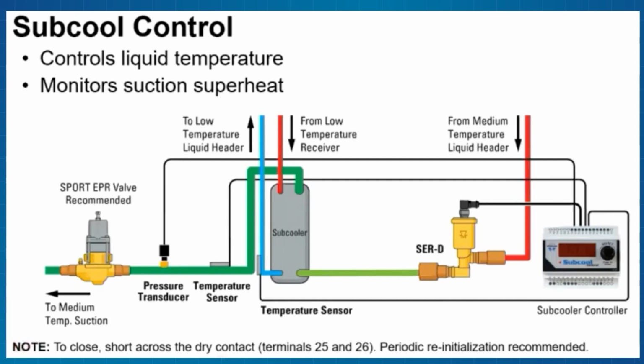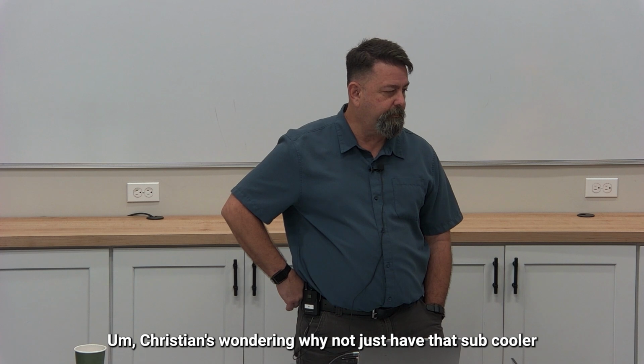So it's gonna go from 100 to 95. Well, meanwhile, now my superheat's climbing. Superheat's climbing because I'm flooded, and I've got liquid going down this pipe, right? And it's going, okay, it's working, let's go to 90. The superheat's still climbing, and it's like, oh, we went too far, let's go back to 95, right? So we can walk in and find this system sitting here at 100% flooding the stew out of everything, and there'd be nothing wrong with it. The problem was it got cool last night, and I turned off the liquid line solenoid.